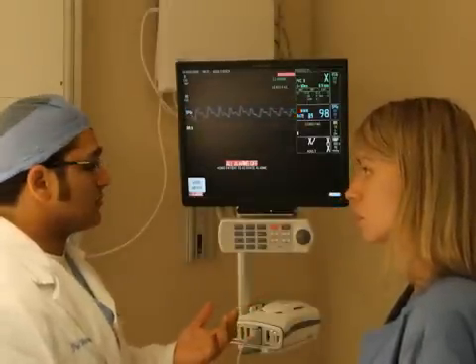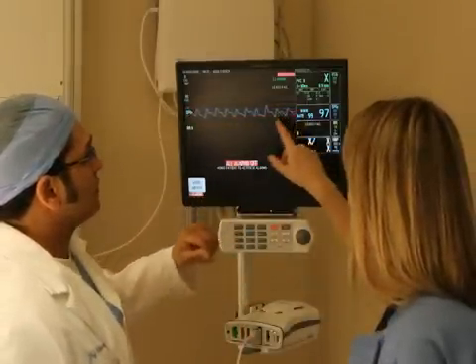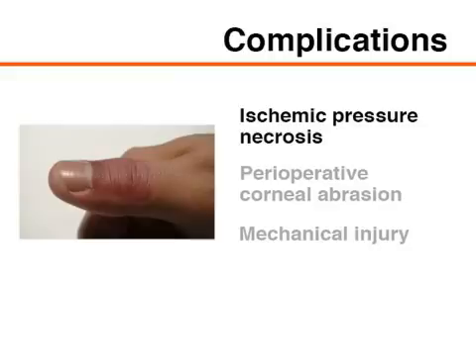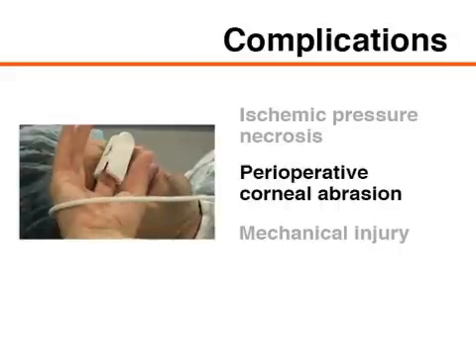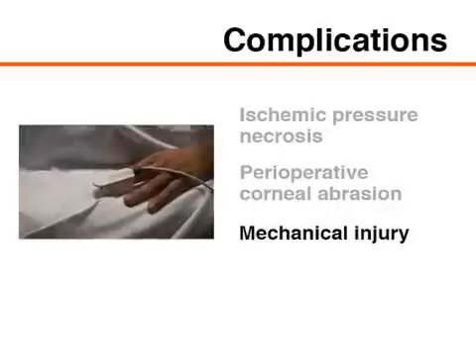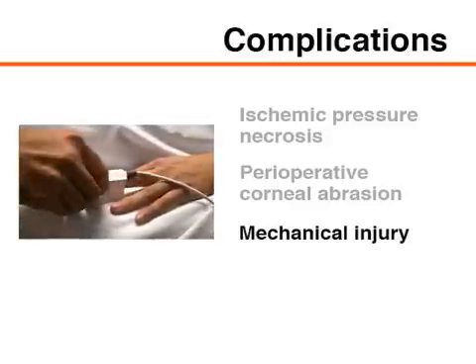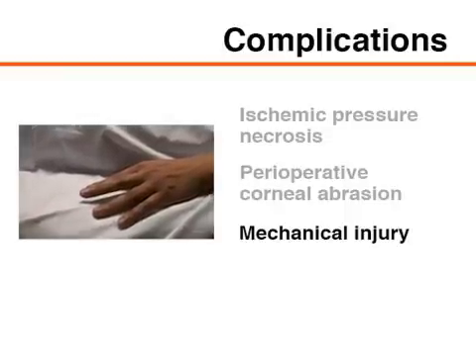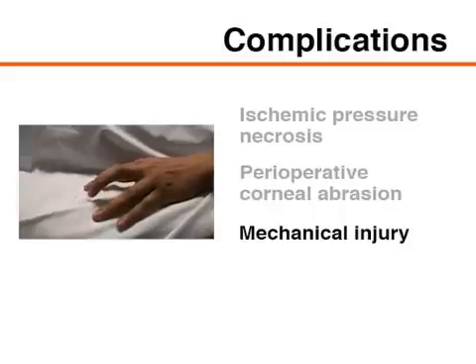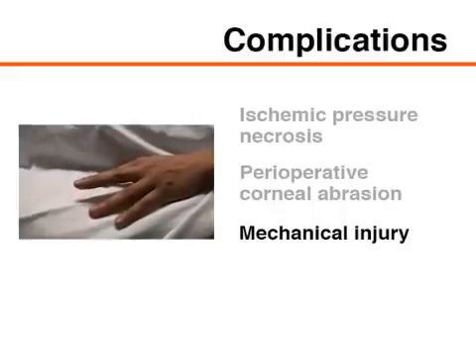Although the pulse oximeter is generally a safe device, its use still carries some risk of adverse events. Ischemic pressure necrosis may result if the probe is placed too tightly on the patient. Perioperative corneal abrasion may occur if a patient with a probe on a finger rubs his or her eyes when awakening from anesthesia. Prolonged placement of a pulse oximeter probe, as may occur in patients in the ICU, may lead to mechanical injury such as finger stiffness, making it difficult to flex the finger after removal of the probe. Although previously documented, these complications remain uncommon.